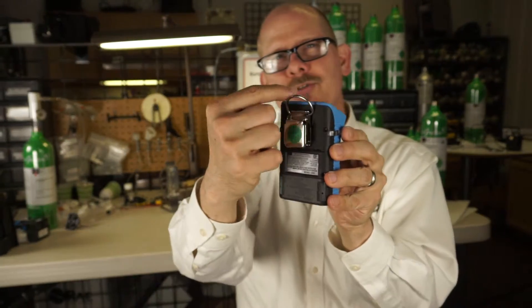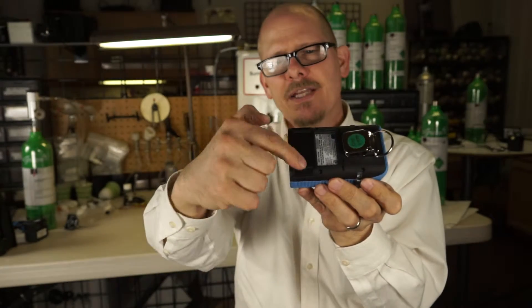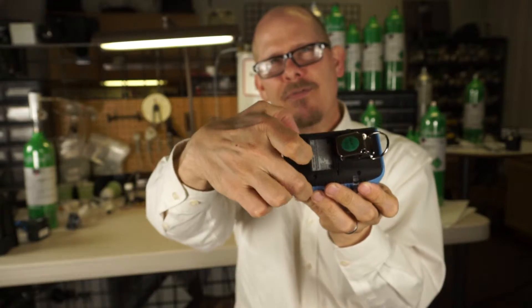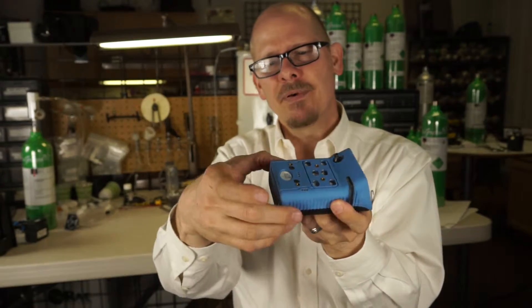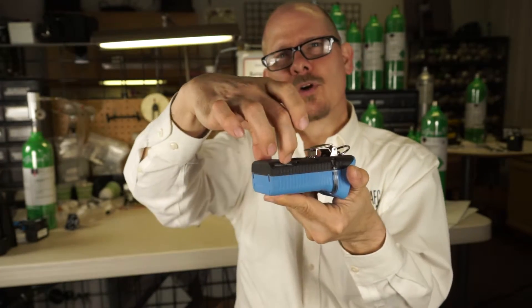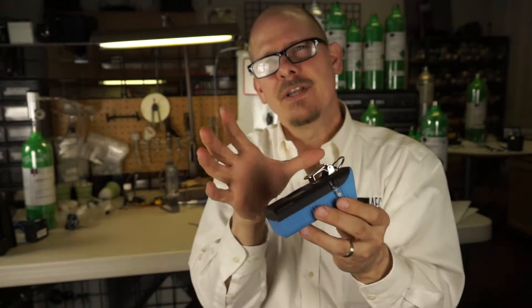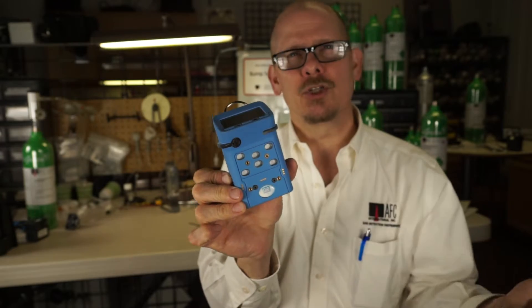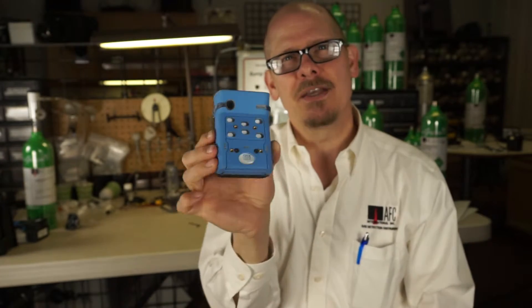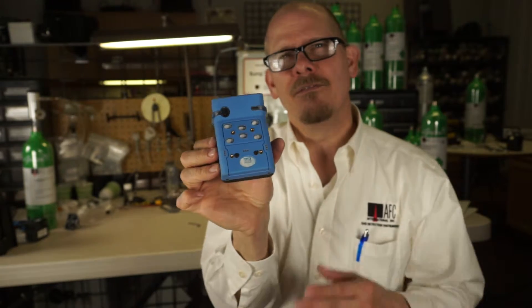As far as the clip goes, there's a traditional D-ring and alligator clip on the back. The battery supply is right here — it has a rechargeable battery, but you can use alkaline as well. Two Allen screws on the front: loosen them and the whole battery pack comes right out. The charger comes with the instrument — very easy, put it in the cradle and latch it down. It's a very nice, solid platform for wall mounting or truck mounting so it won't be flying around.